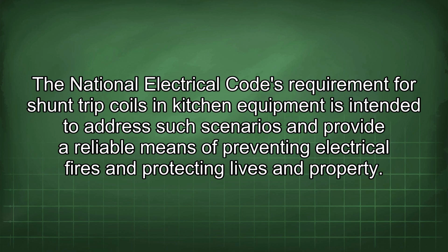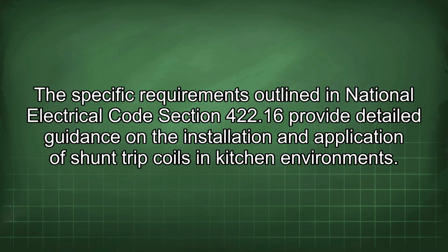The National Electrical Code's requirement for shunt trip coils in kitchen equipment is intended to address such scenarios and provide a reliable means of preventing electrical fires and protecting lives and property. The specific requirements outlined in National Electrical Code Section 422.16 provide detailed guidance on the installation and application of shunt trip coils in kitchen environments.